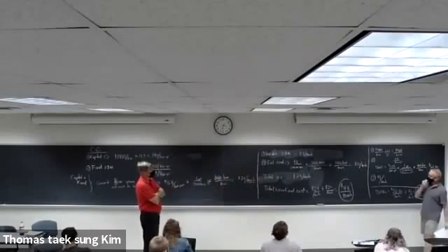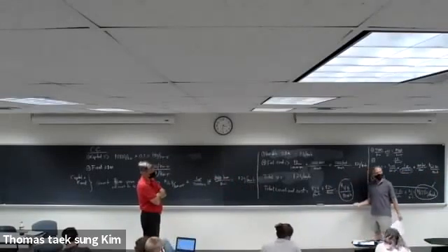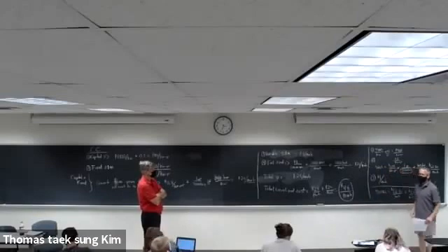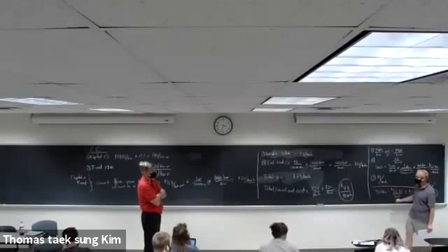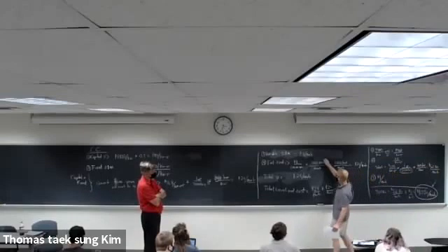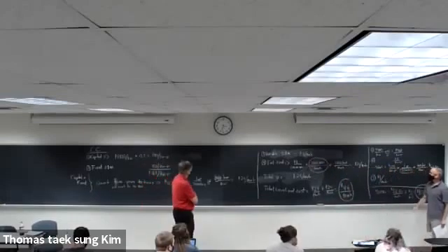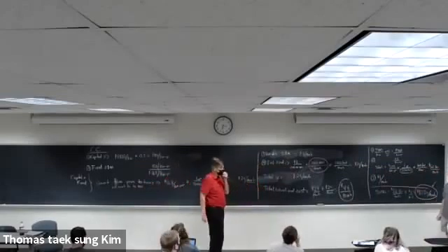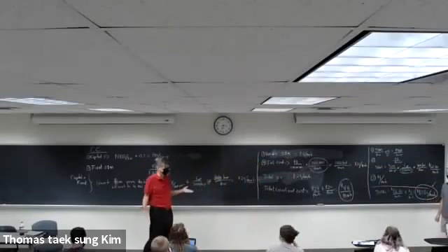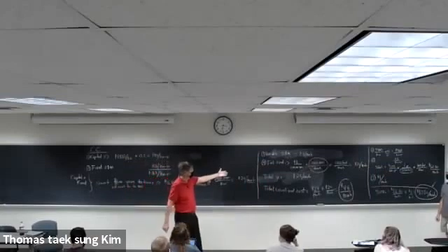The other interesting thing on these calculations is that you can start to see what factors affect these decisions when you're thinking about building plants. The capacity factor makes a huge difference, and the heat rate over here makes a huge difference. If you cut that down by 25%, these costs go down a lot. Fuel costs will affect it as well. Fuel cost is high now. Today it's $4. When we did this example, it was less than 3. It was actually 2 last year.